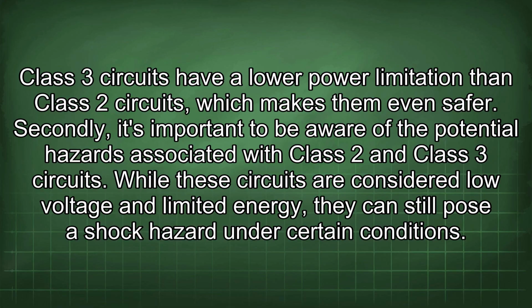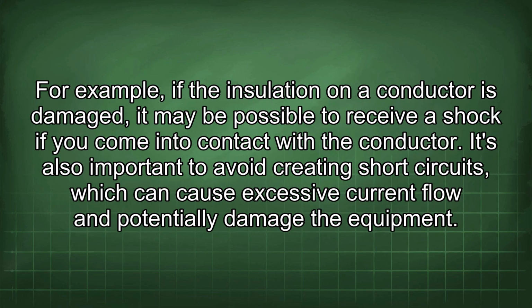Secondly, it's important to be aware of the potential hazards associated with Class 2 and Class 3 circuits. While these circuits are considered low voltage and limited energy, they can still pose a shock hazard under certain conditions. For example, if the insulation on a conductor is damaged, it may be possible to receive a shock if you come into contact with the conductor. It's also important to avoid creating short circuits, which can cause excessive current flow and potentially damage the equipment.